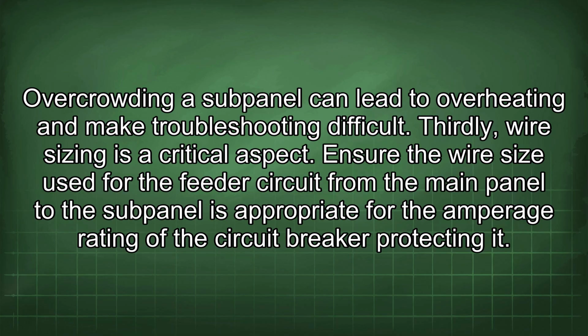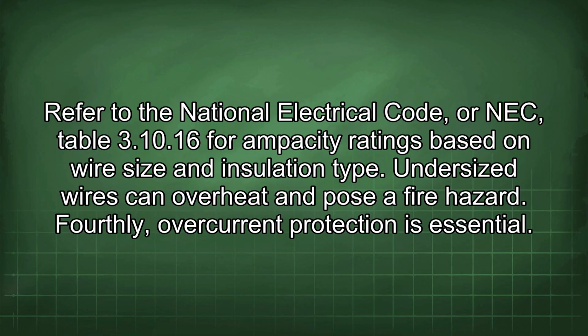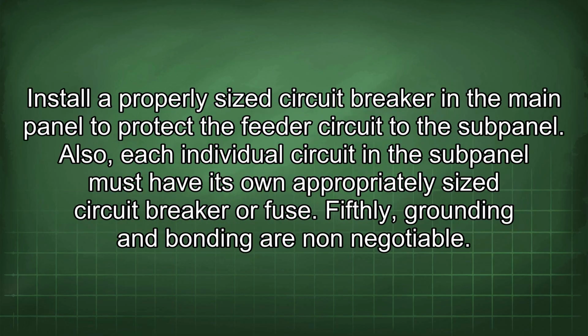Thirdly, wire sizing is a critical aspect. Ensure the wire size used for the feeder circuit from the main panel to the subpanel is appropriate for the amperage rating of the circuit breaker protecting it. Refer to the National Electrical Code, or NEC, Table 3.10.16 for ampacity ratings based on wire size and insulation type. Undersized wires can overheat and pose a fire hazard. Fourthly, overcurrent protection is essential. Install a properly sized circuit breaker in the main panel to protect the feeder circuit to the subpanel. Also, each individual circuit in the subpanel must have its own appropriately sized circuit breaker or fuse.